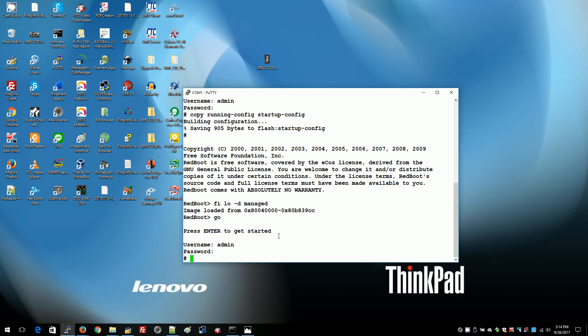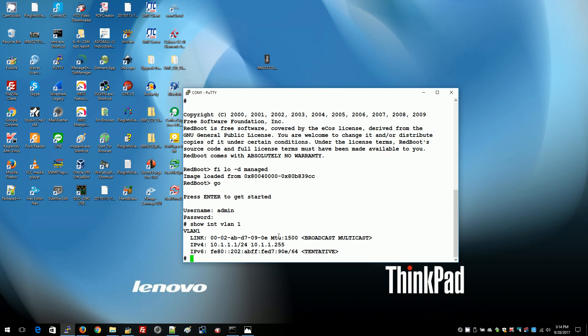And there we go, we're in. And the factory default IP is 10.1.1.1. So at this point you can continue to configure with the CLI or you can connect with the web or you can change IP address and then connect with the web.